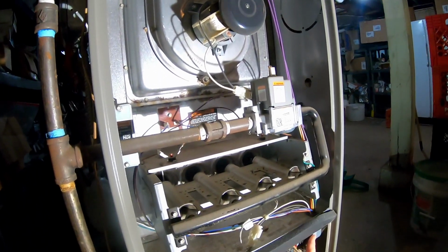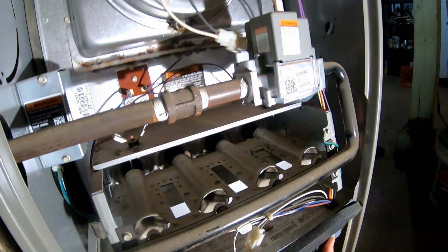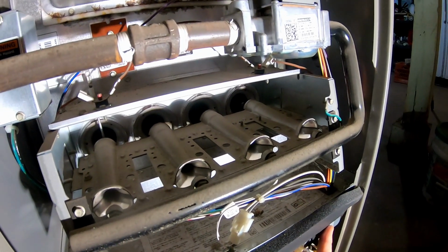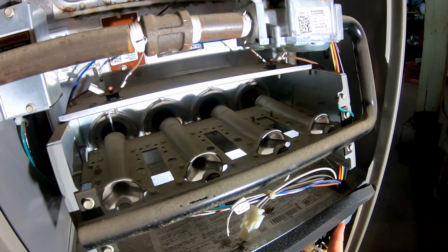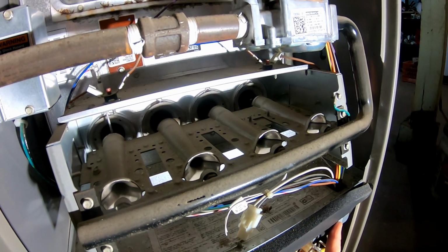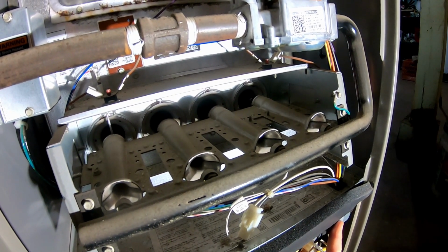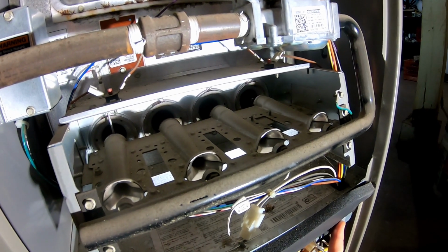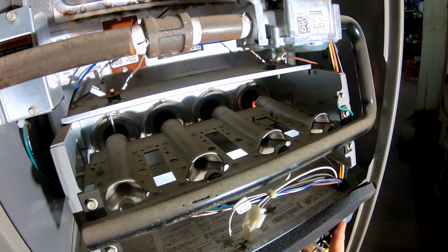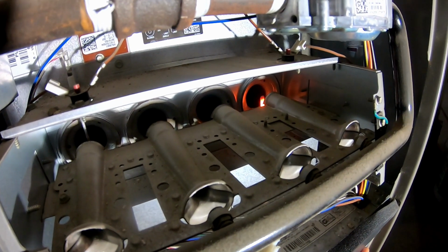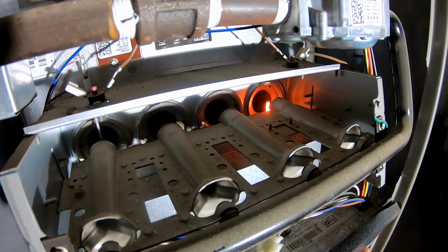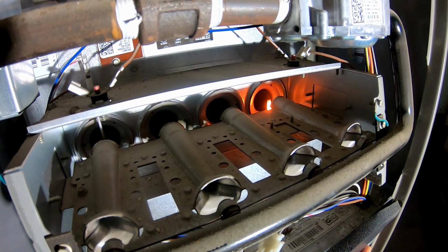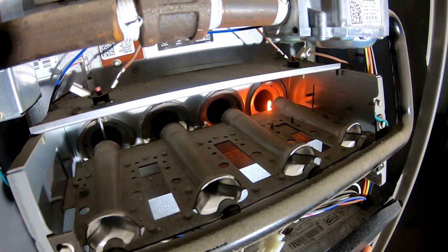Now you can hear that the fan started, and now we're going to be watching for the igniter to start to glow. And it does take a few seconds here, so I'm doing it real time so you can kind of see that it does take a little bit of time. And it should pop up. Here it goes, and you can see it's slowly getting red, and it has to get to a high enough temperature before the safety will release the gas. And so it should happen here in a second now.